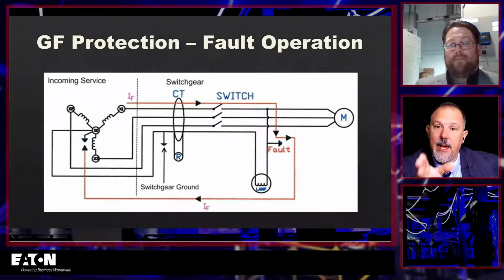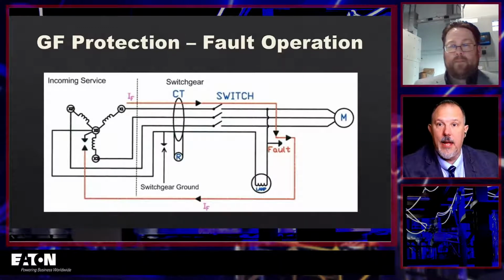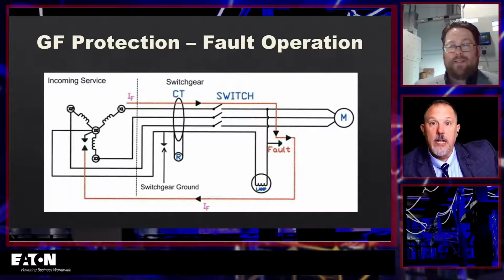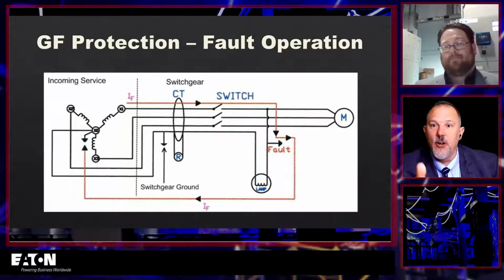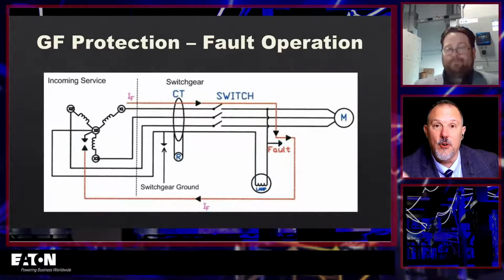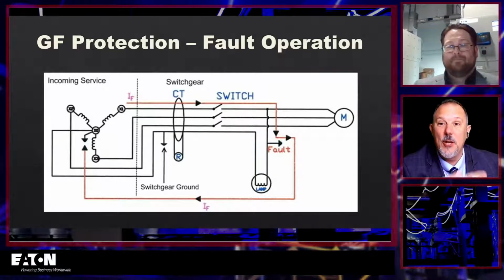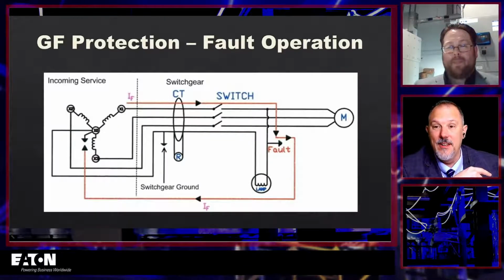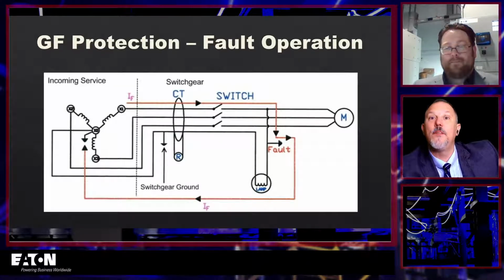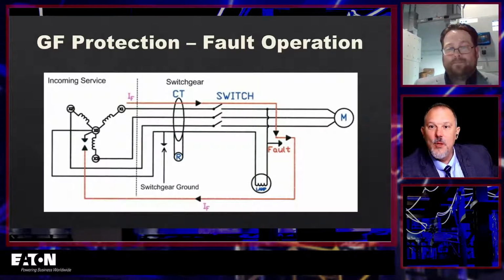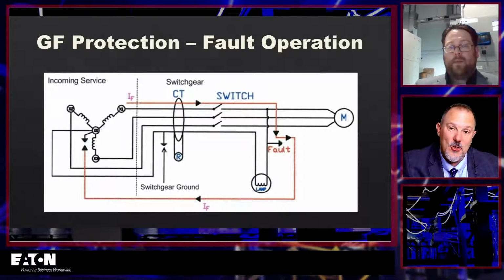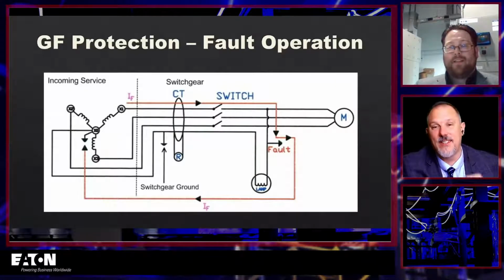And I know other electricians who have told me stories of taking the main out, and they couldn't figure out why it tripped the main and not the smaller breaker that was feeding it. It was because the current was so low, because of the ground fault current and the impedance in the path, that it did not trip the device feeding it, but it tripped the ground fault protection, which, if you had it closer, you would have taken off a branch circuit instead of a main.